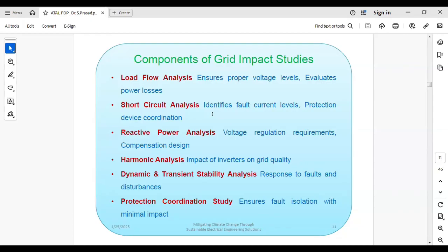So those things will be investigated so that the breaker will be designed. What is the circuit breaker? What should be the size of the circuit breaker? What should the types of protecting device be, connected so that the system will be protected if a short circuit happens? So we have to go for a short circuit analysis, produce a report and submit it to the utilities. Okay, so I will consider a practical case study, and I will conduct a short circuit analysis also.